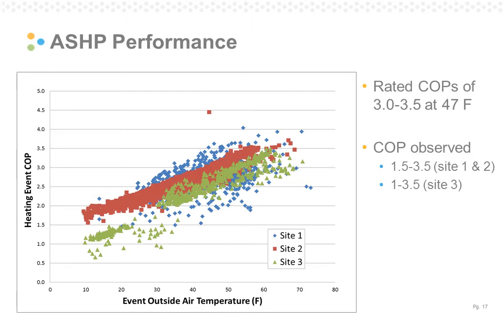At Site 3, we are seeing some lower COPs during the colder temperatures, which we're going to investigate this heating season. But in the warmer temperatures, we are seeing COPs of up to 3 to 3.5 at all three sites, and the rated COPs of each of these systems at 47 degrees is between the 3 to 3.5 range.